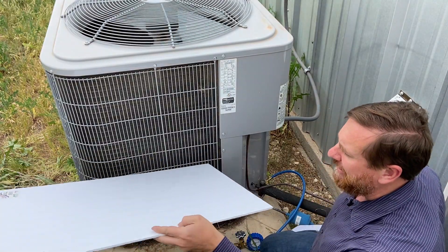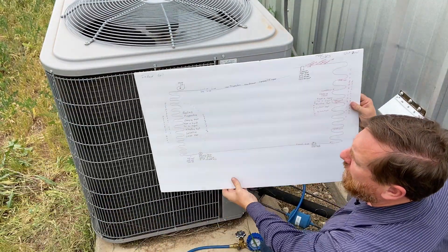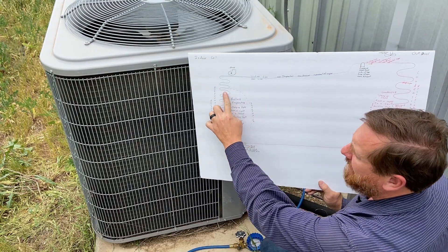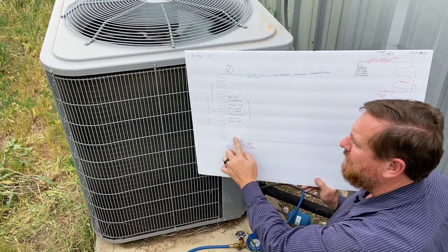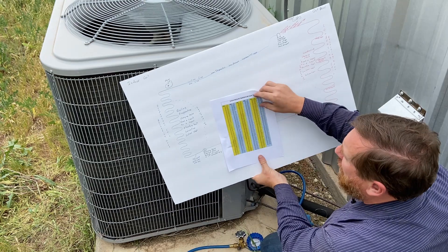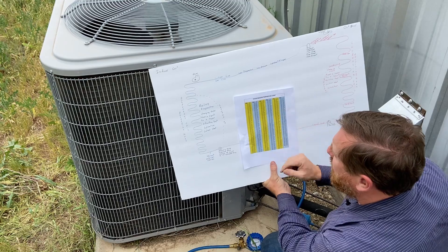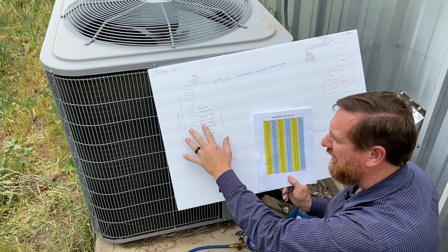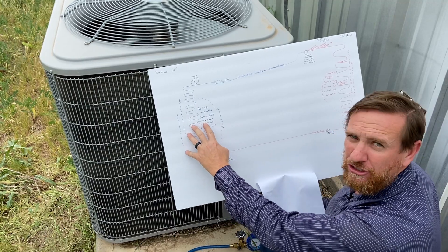That also means my boiling point is 52.5°F. Looking at our refrigeration cycle, right past the metering device through most of the indoor unit, this is where the refrigerant is boiling. We can compare 150 psi to 52.5°F — the refrigerant is boiling at 52.5 degrees, changing state from a liquid to vapor, absorbing massive amounts of latent heat. By controlling the pressure, we control the boiling point of the refrigerant.